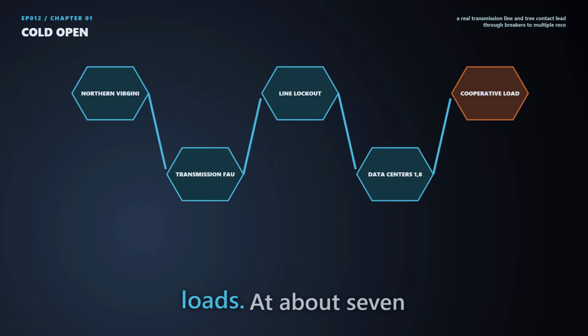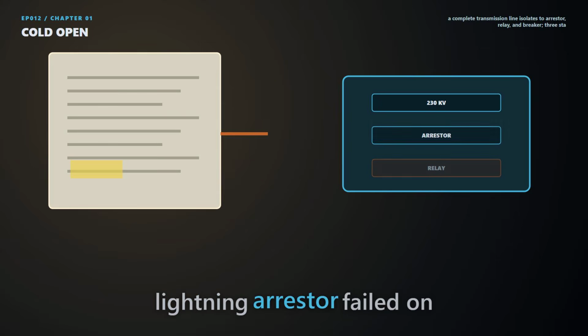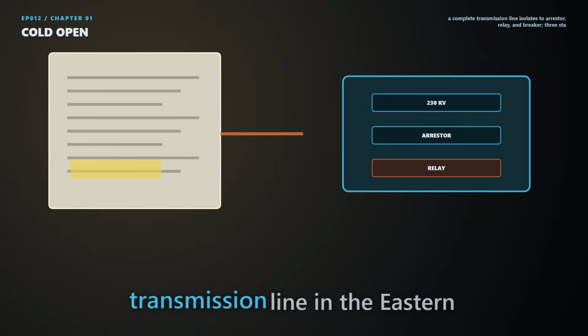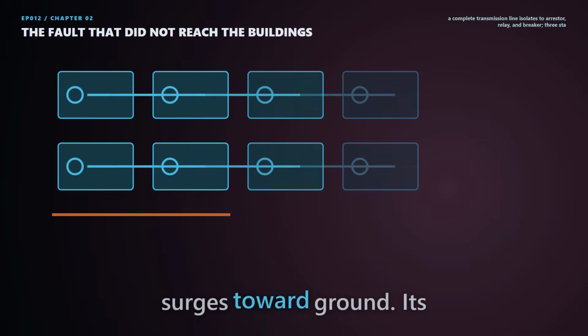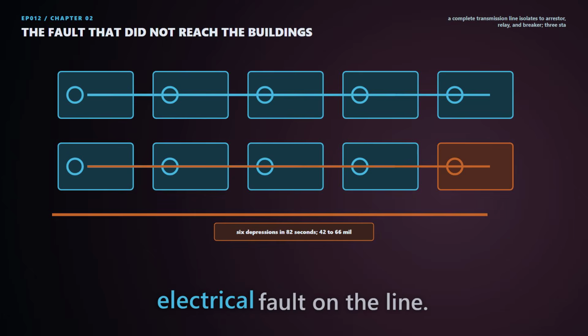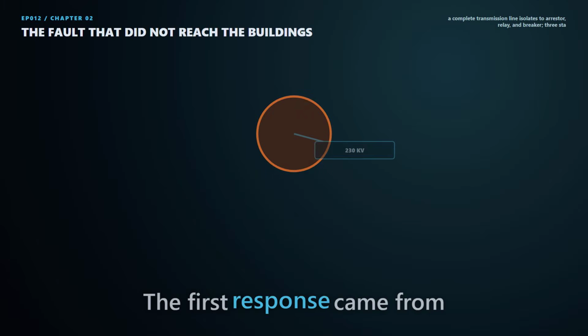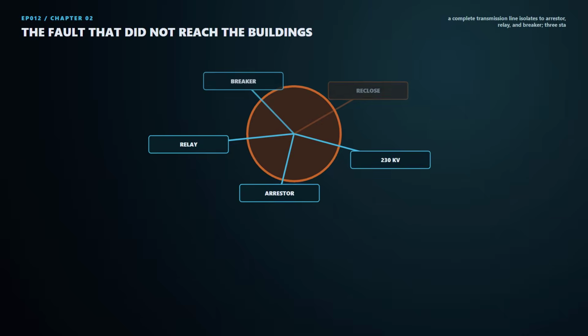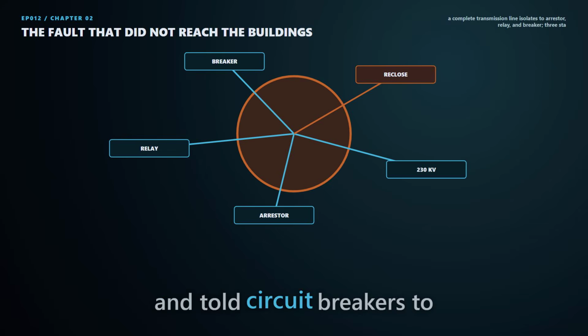Virginia connects large loads. At about 7 in the evening on July 10, 2024, a lightning arrestor failed on a 230 kilovolt transmission line in the eastern interconnection. The device normally shunts dangerous surges toward ground. Its failure left a permanent electrical fault on the line. The first response came from transmission protection. Relays detected the abnormal current and told circuit breakers to open.